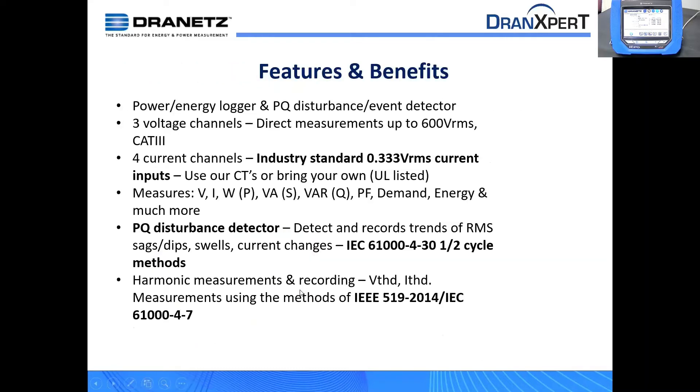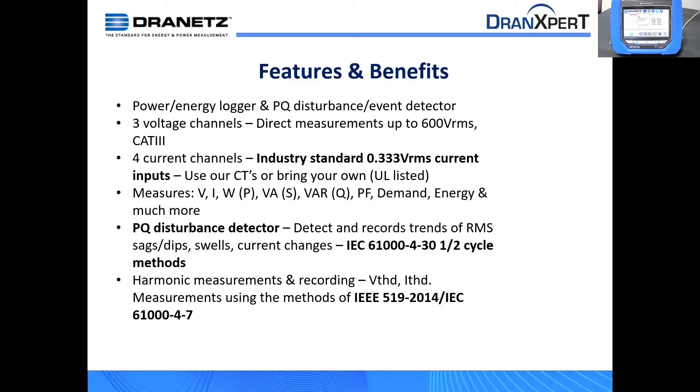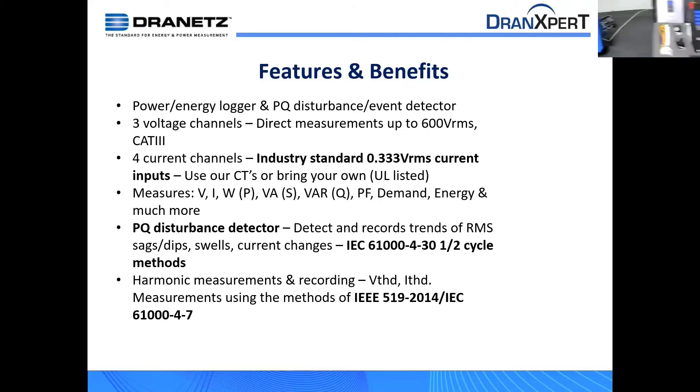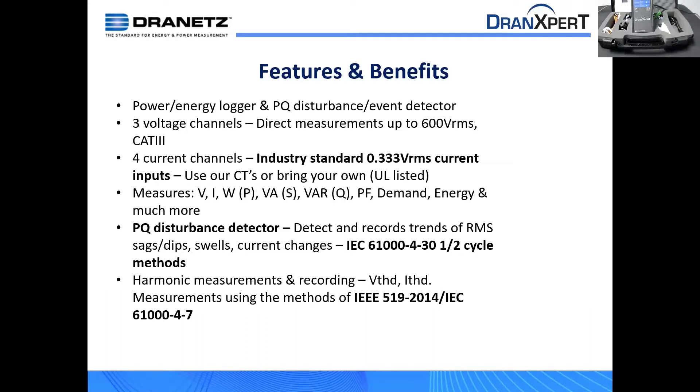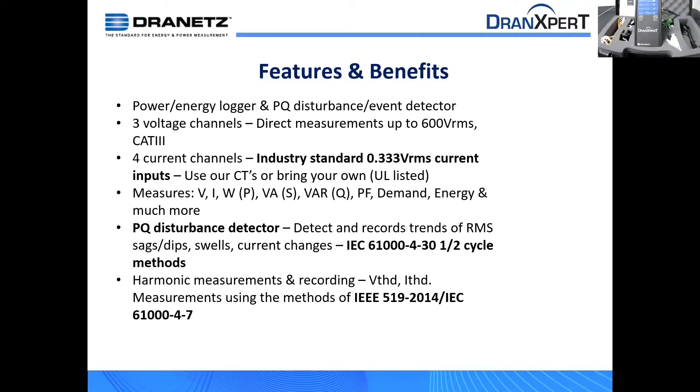So just a brief review of the features, and then I'll turn it over to Thurman. He'll do a demonstration. So it is a power and energy logger. It has direct connections up to 600 volts. It has three voltage channels and four current channels. That fourth current channel would be for maybe neutral loading and things like that to look at your neutral current. So we do use an off-the-shelf standard 0.333 volt input for our current inputs. So you can buy CTs from Dranetz, or you have the ability to use your own off-the-shelf third-party CTs that support this input. This is a standard one. However, we'll warn you, just please choose a safe CT. In the United States, we recommend a UL-listed CT. Our products are UL-listed. This product is UL-listed, as well as our accessories, including CTs, are UL-listed.